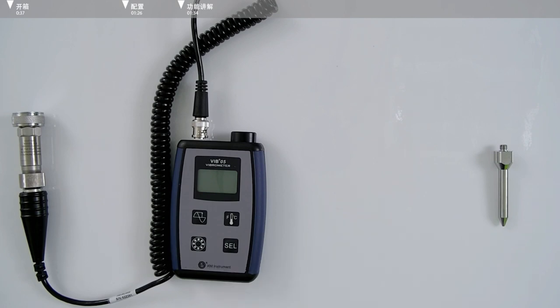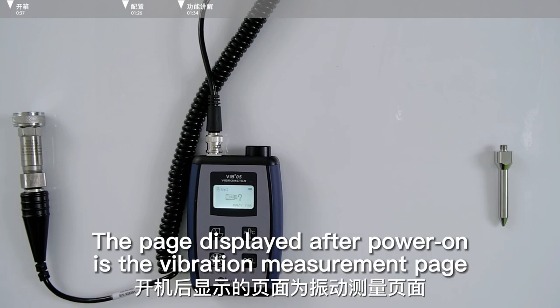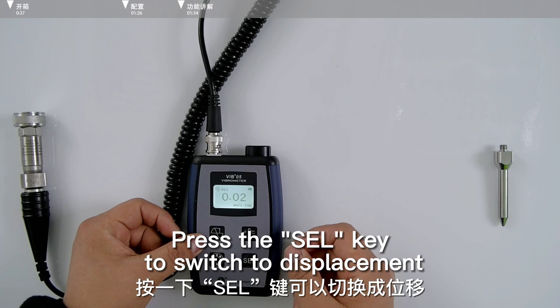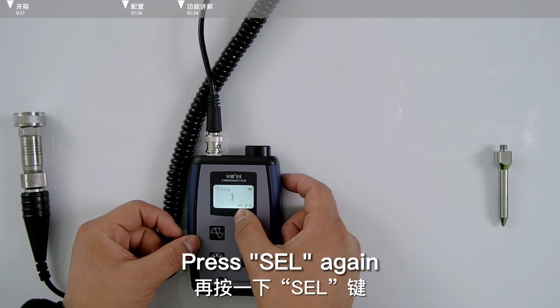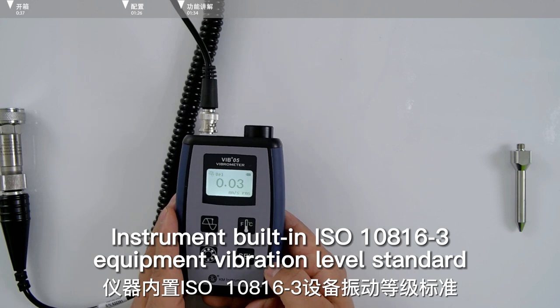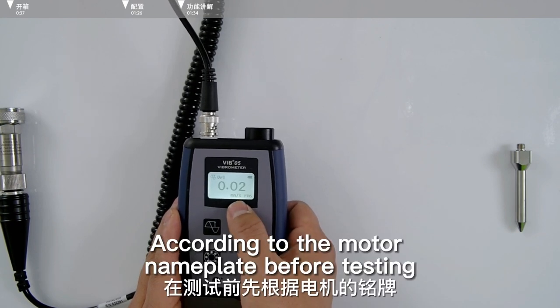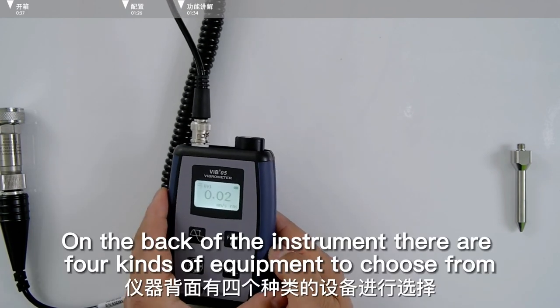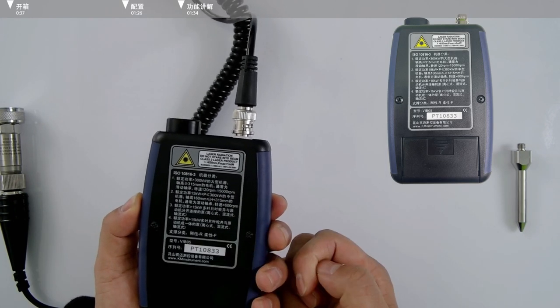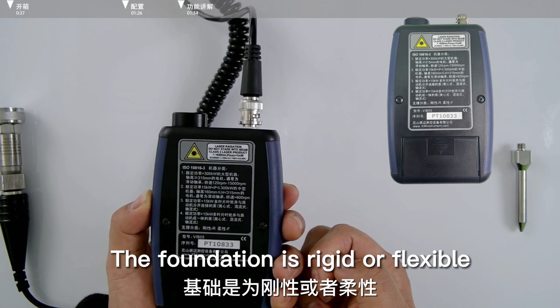Start the machine before testing. Press the SEL key to power on. The page displayed after power on is the vibration measurement page. There are three physical quantities in vibration measurement: the first is speed with unit MM/s, press the SEL key to switch to displacement with unit µm, press again to switch to acceleration with unit G. The instrument has the ISO 10816-3 equipment vibration level standard built in. According to the motor nameplate, before testing select the right equipment type on the back of the instrument — there are four kinds of equipment to choose from.